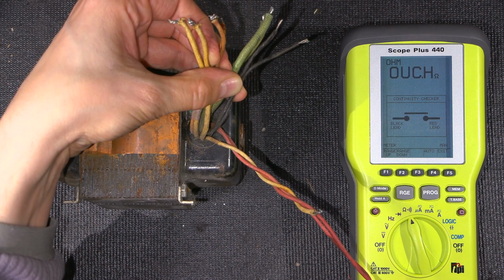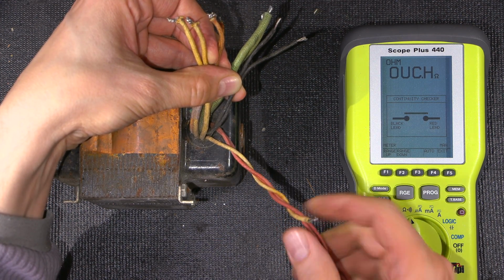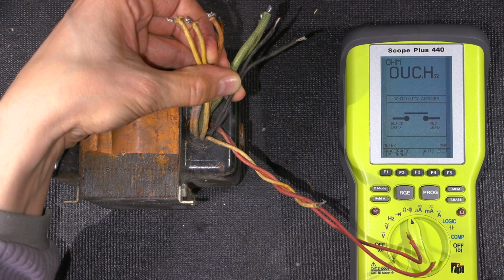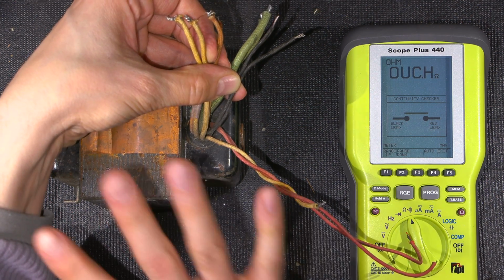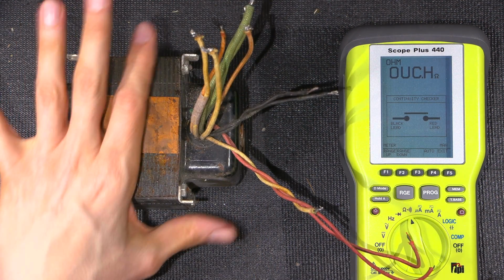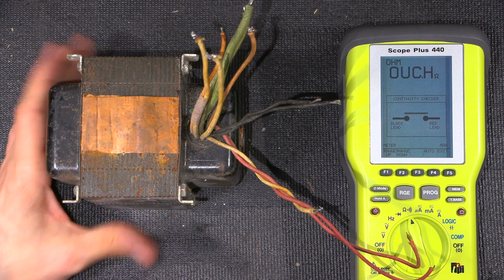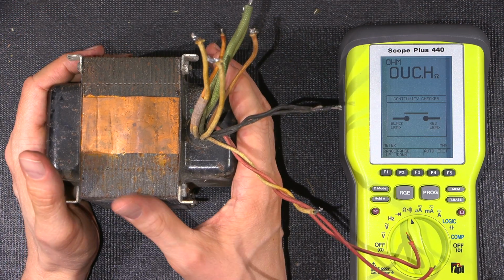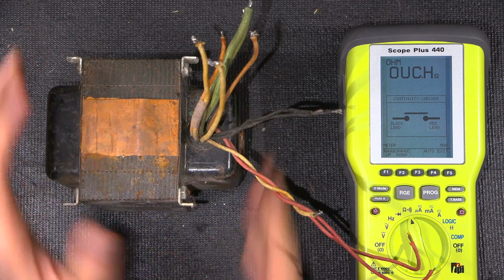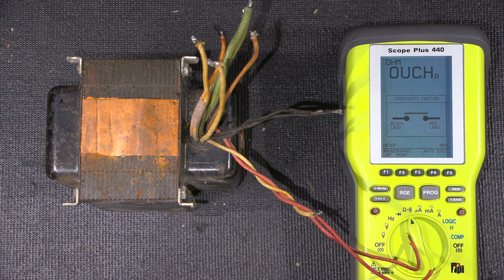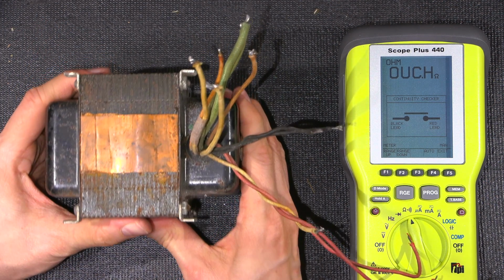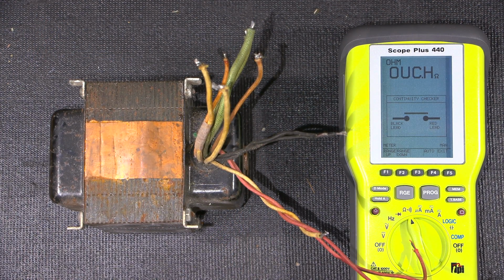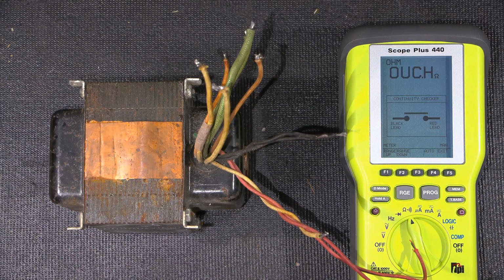Very commonly in a power transformer like this, you have a center tap on the high voltage winding, and that's exactly what this is. You never want to do this type of test with any type of voltage or current applied to the transformer, because that could be a very, very dangerous situation. So you always want to make sure that the transformer is completely disconnected from anything before you test anything the way that I just did. Again, this is just an ohm test. That's all we did. No voltages or anything, no current is present on this transformer or coming out of this transformer.